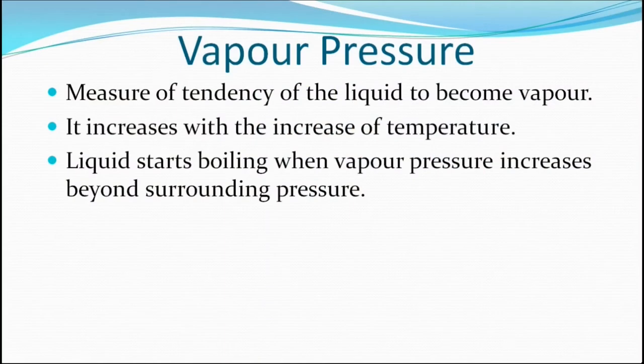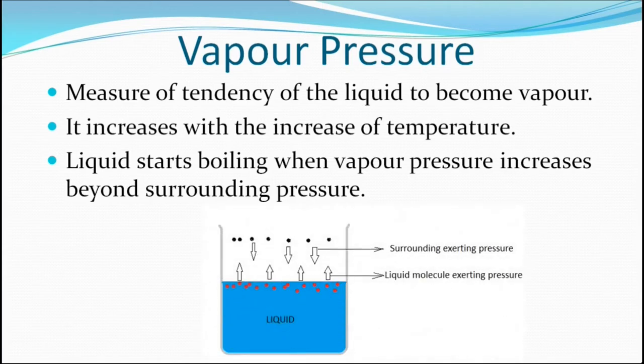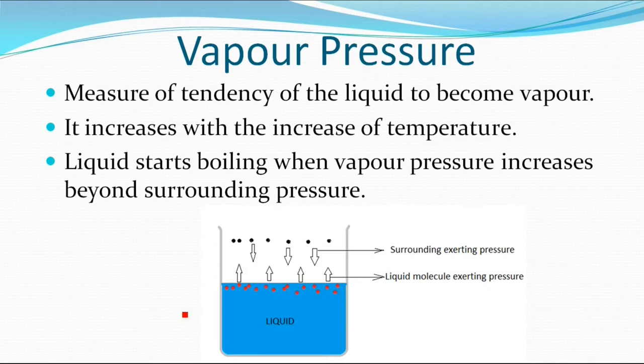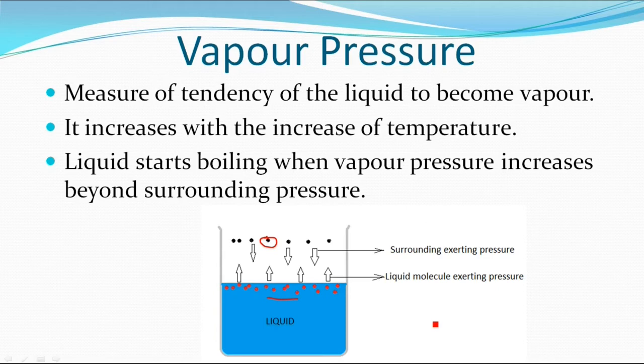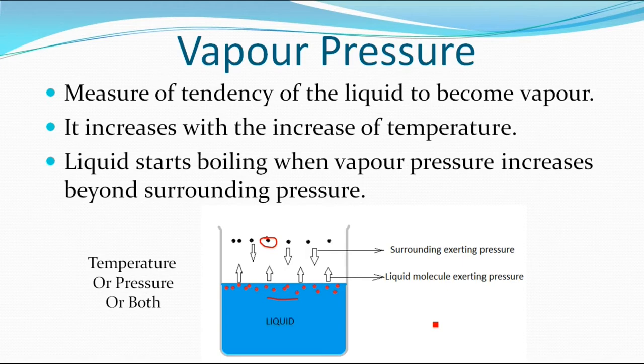To understand cavitation, first we have to understand vapor pressure. Vapor pressure is a measure of the tendency of a liquid to become vapor. In this diagram, the red dots are water molecules trying to exert pressure on surrounding molecules, and the black dots are surrounding molecules trying to exert pressure on the liquid surface. Boiling or steam formation starts when either the surrounding pressure decreases beyond the vapor pressure of the liquid, or the vapor pressure of the liquid increases above the surrounding pressure. This can be done by altering temperature, pressure, or both. Heating the liquid increases its vapor pressure, so boiling starts. Similarly, decreasing the surrounding pressure below vapor pressure also starts boiling.